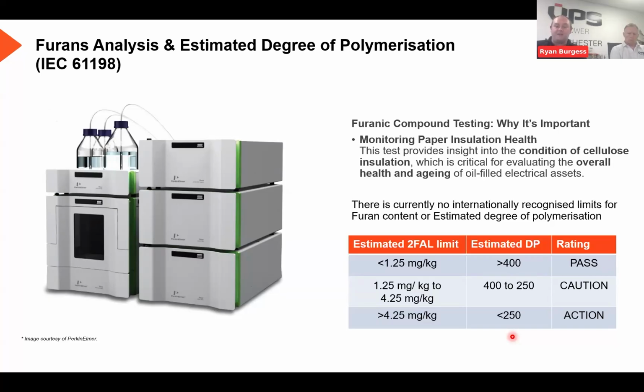So if it's an asset that's used to going from high load, low load, high load, low load, you definitely want to reduce that. Or if it's at a constant high load, you want to reduce the load and the stress that it's under to help prolong the life of that paper. But ultimately, you need to also look after the oil itself, as we said, as that starts degrading, that will speed this up as well.